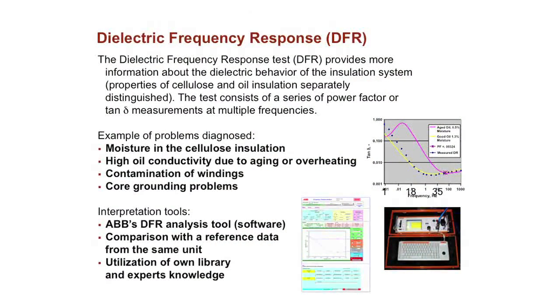Now, another diagnostic test is a dielectric frequency response. It is across a frequency spectrum, but instead of measuring the voltage as with SFRA, this is measuring the power factor across the frequency spectrum. So this is more looking at whether there's been changes in the dielectric strength of the insulation, within the windings or from the windings to ground. Again, this is only something you would do if you see some kind of issue with the transformer.